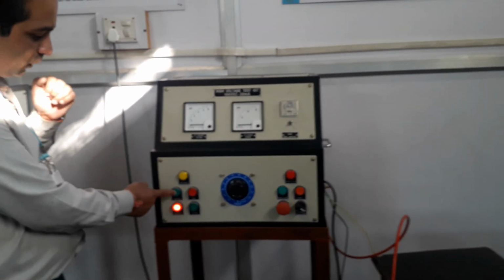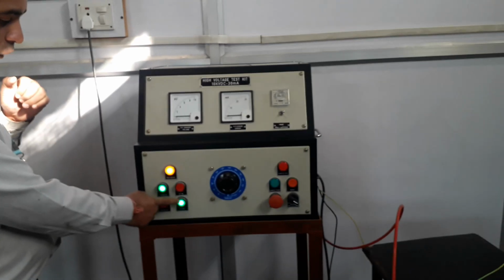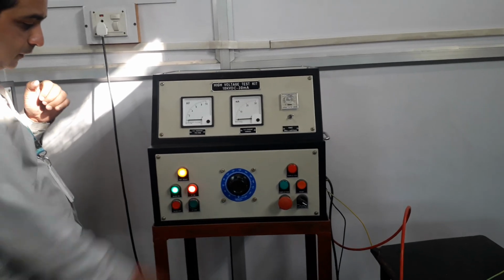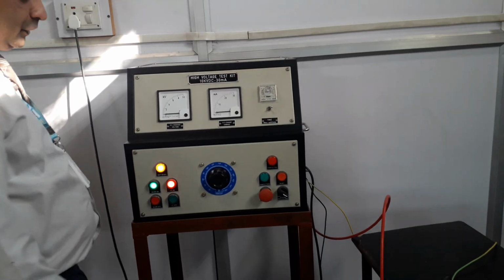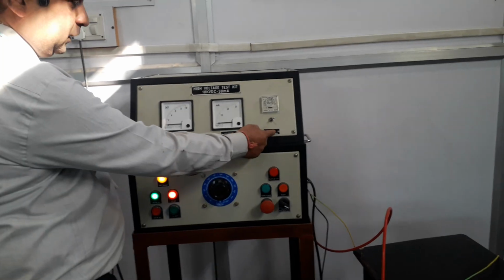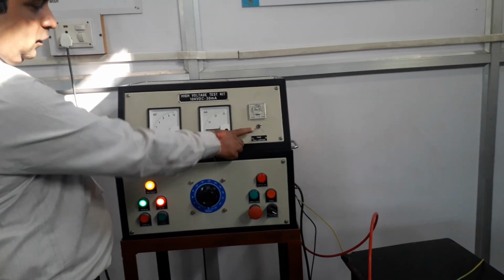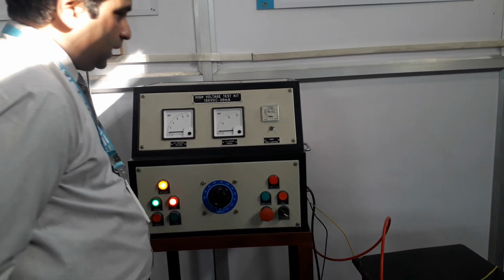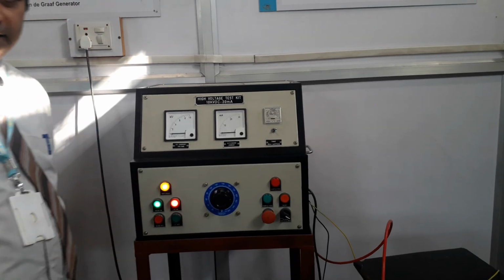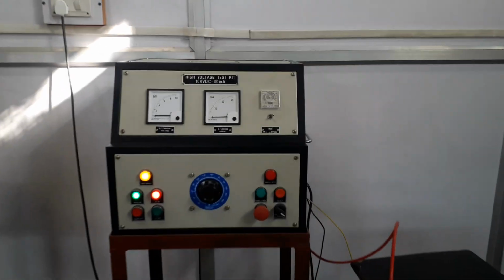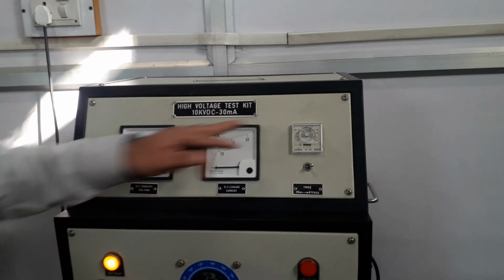Okay. Now we are going to apply mains on. We switch on the mains on, ST off, and ST on. Now you will apply the high voltage. Simultaneously, you switch on the timer. For example, for a particular instant of time, here we have taken 6 seconds. You are able to see that you are applying 4 kilovolts for 6 seconds.